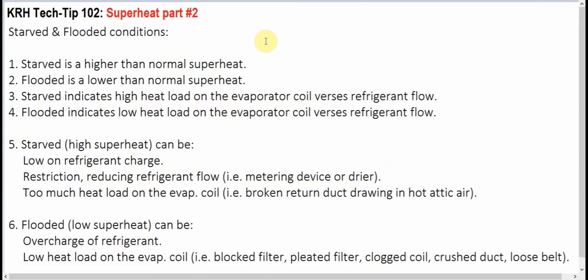Now, I want to get into the different conditions that we look at in regards to superheat, and those conditions are starved and flooded. Starved condition is a higher than normal superheat. Superheat range we had just talked about, that temperature is higher than that range, and we consider that to be starved. Flooded is the opposite. It is a superheat that is lower than the normal superheat. Starved indicates high heat load in the evaporator coil versus refrigerant flow. Flooded indicates low heat load in the evaporator coil versus refrigerant flow. And you're checking the boiling point versus the suction line temperature to get superheat.